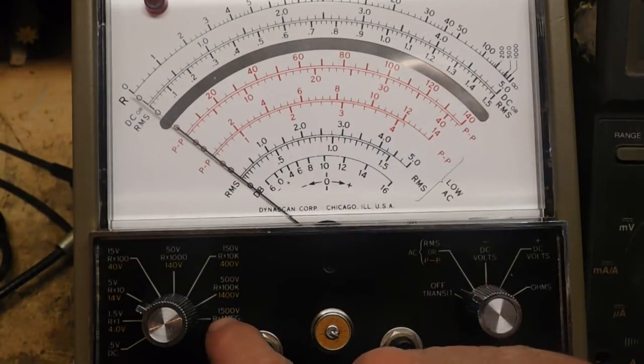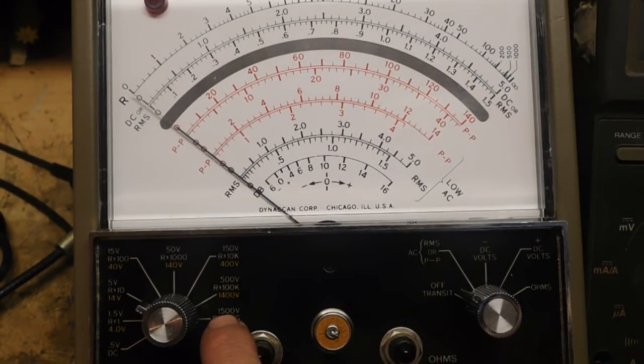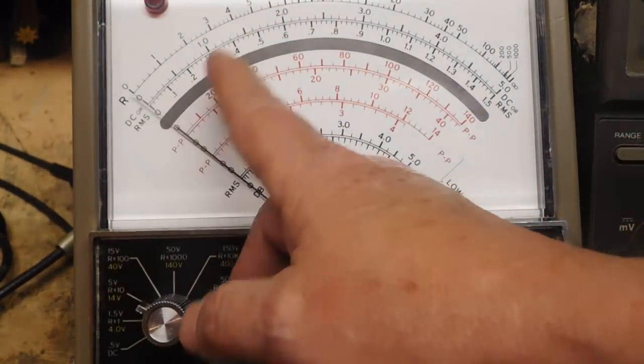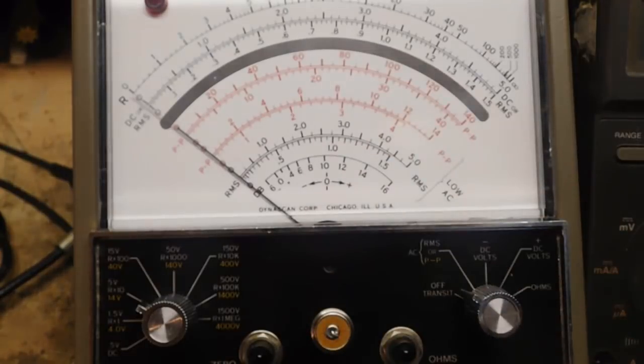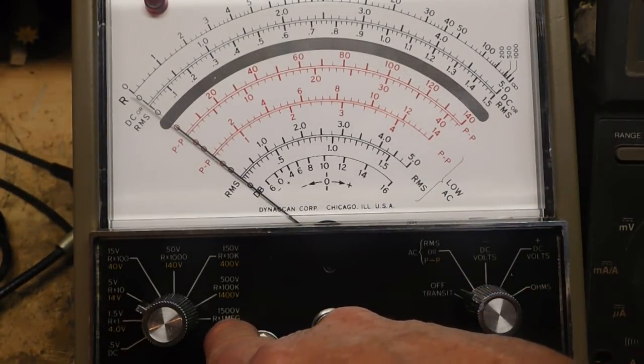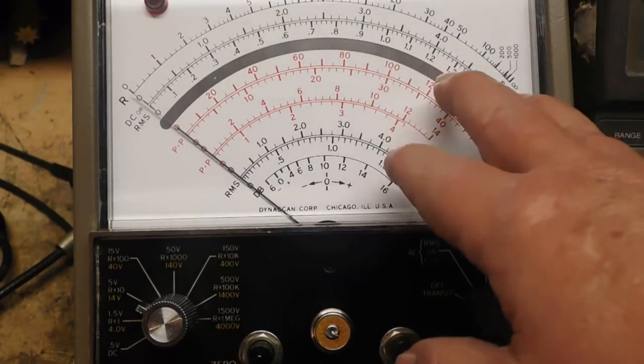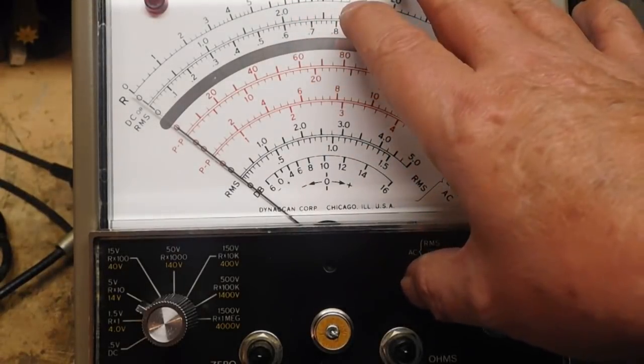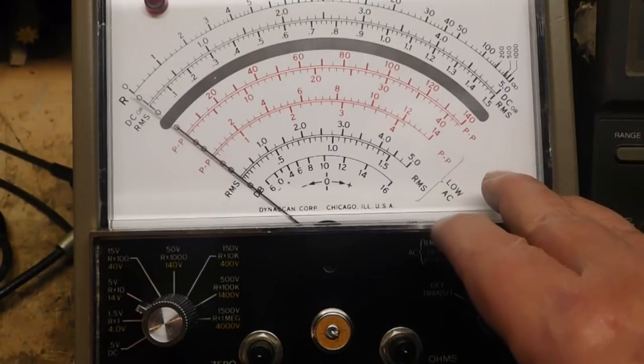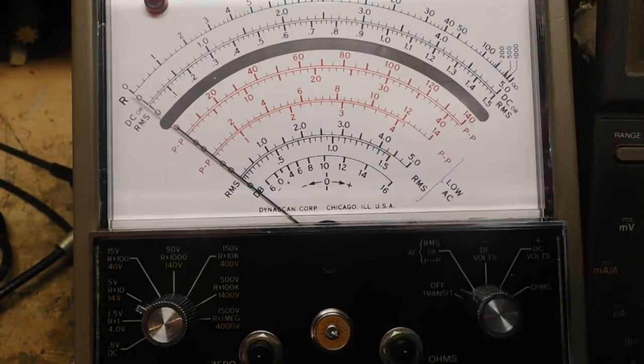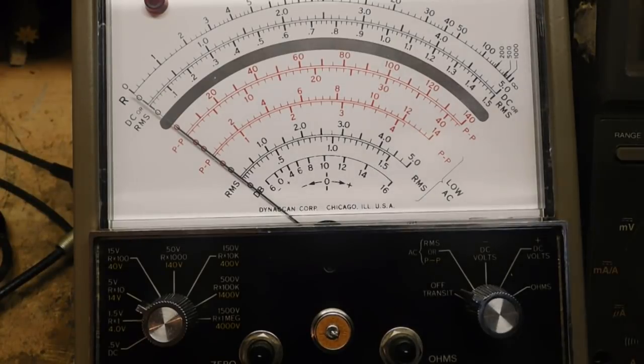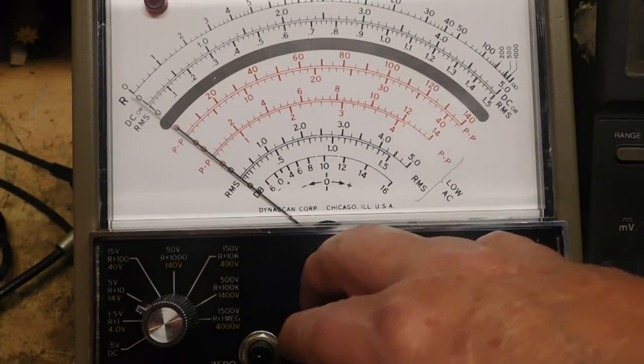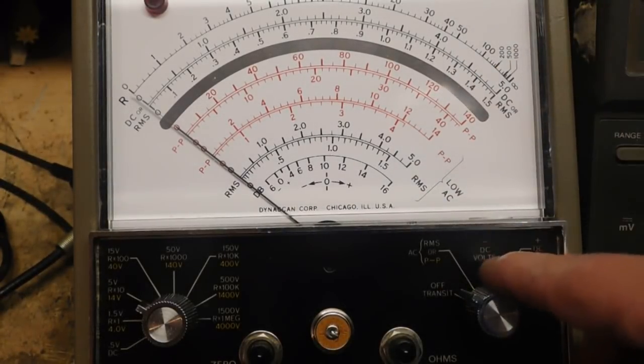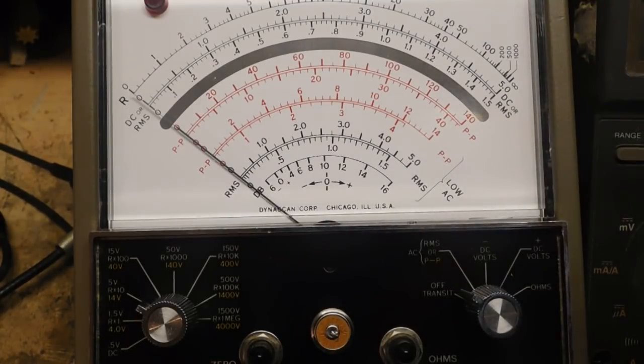When you don't know the voltage, the safest bet is to set it to your highest scale. If it's reading way down low, you can move it down to the next scale until you get it reading someplace easier to read. That way the meter movement is well protected and you don't have to worry about banging the needle. You do need some idea what it is, so you're not measuring something that might have 10,000 or 5,000 volts on it - that would not be good. But that's basically the answer to the question.